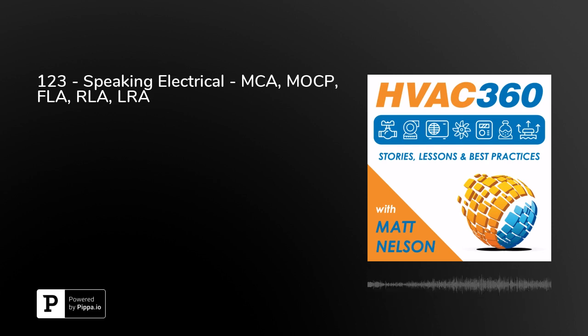Now, here's where it gets a little bit confusing. There's two others that are similar in sound and kind of look similar, and these are all talking about amps, so it's kind of confusing if you haven't gone through it. So we've talked about FLA. Now we're going to talk about LRA, or locked rotor amps. This is used to gauge the amount of starting current of a motor, which can be up to 8 times the full load amps. This is often used by electrical engineers to calculate the maximum voltage drop during motor starting. Now, this is critical. We talked about full load amps. That's for when it's already running. But when it goes from a dead stop to running, it's going to draw a lot more current, and that's the starting current that the locked rotor amps is referring to.